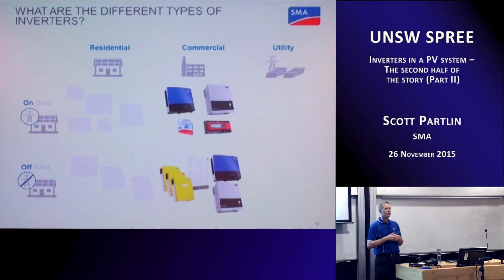You need to, rather than having single units per phase, you might need multiple units per phase, the ability to provide fault current, and the ability to cope with peak loads or kick-on loads from AC motors or other such devices.